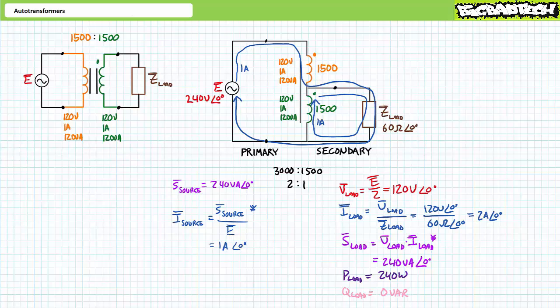Consider the amount of power capable of being transferred by the auto transformer. When configured as a traditional transformer, 120 volt ampere input resulted in 120 volt ampere output, and the transformer weighed eight pounds. Configured as an auto transformer, the same eight pound transformer uses both windings — each with a 120 volt and one amp rating — and transfers a total of 240 volt amperes of power. This suggests auto transformers can transfer more power in a smaller, lighter, less expensive package. However, the single winding serving as both primary and secondary defeats the isolation feature of a traditional transformer. Note that a doubling of power rating is the maximum one might expect to achieve for an auto transformer; other turns ratios do result in more power transfer, but not quite double.